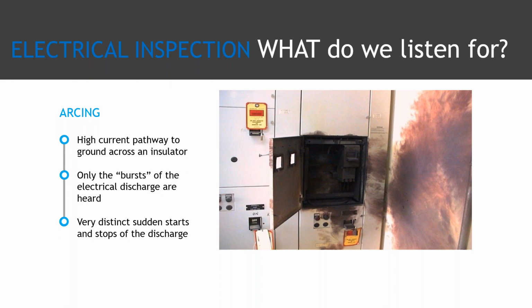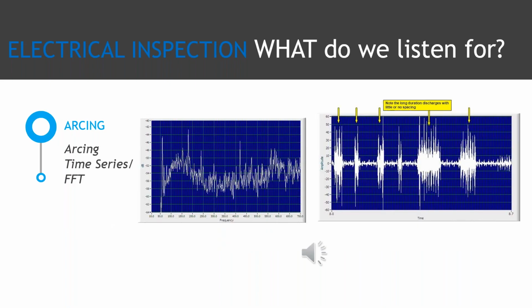Arcing, the most dangerous of the anomalies we'll hear with ultrasound, is a high current pathway to ground. You'll hear a lot of bursts of energy, popping, cracking, very distinctive starts and stops of this discharge. That's a very dangerous situation.